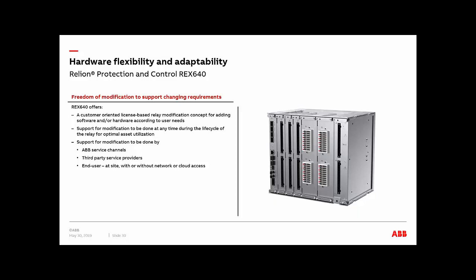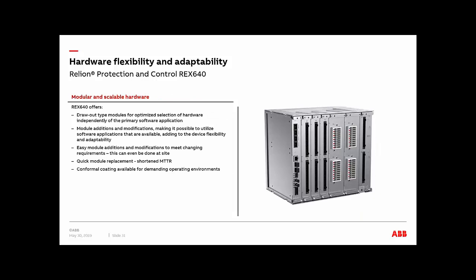So pretty much the 640, what does it offer? Well, a customer can have a license where you have your original purchase packages, but you could do modifications anytime during the life cycle of the relay, which would allow you to either expand or change the hardware, or change some application from CTs to current sensors. So this is very, very flexible, and it will give you the possibility of having a completely different relay from whatever you ordered at the beginning, anytime during the life cycle of the product. The modules on the relay are the draw type, and you can simply remove the cards, replace them, and change them for the ones that you want. If any of the packages that you have, for example, require new hardware, you can easily do it on site with instruction from ABB and, of course, the proper procedures.